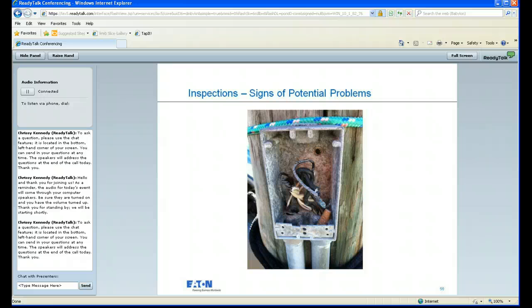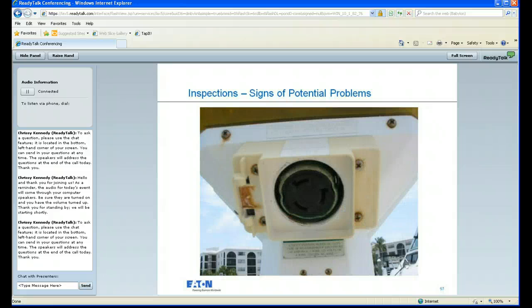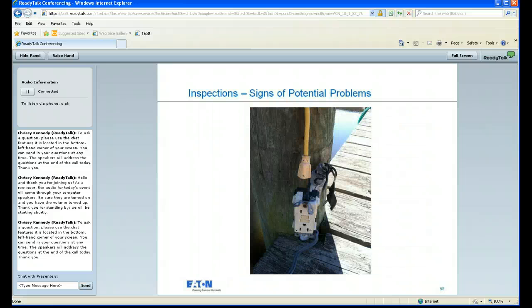Any sort of exposed wiring, these appear to have been capped off or turned off a while ago, but anything like that should be covered up in any way that you can. Missing parts and component pieces, having an exposed door like this, can lead to damage to the receptacle. Looking for circuit breakers that are exposed, things like that, can be taken care of very easily by contacting your equipment manufacturer.